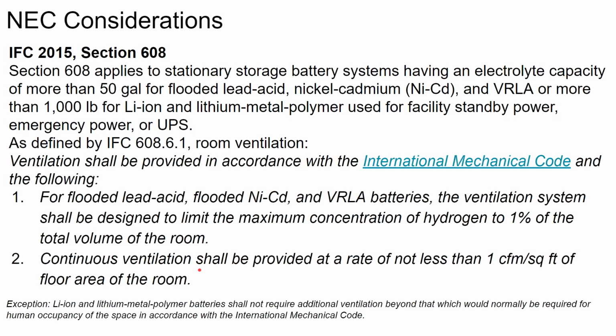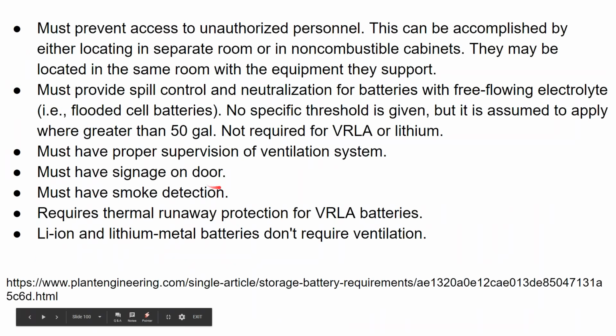What you'll often get is a dedicated battery box with a fan inside the battery box to blow air through the enclosure of the batteries to make sure that the area around the batteries is continuously vented. So it's more common to locate the batteries in a room that is adjacent to the outdoors, and then put a box, even if you're inside of a garage or inside of a room, to enclose the area where the batteries are and vent directly to the outside, even if the room is otherwise air conditioned.